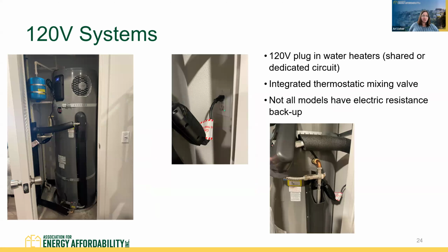120-volt systems. Now, these are pretty interesting because it's essentially a plug-in heat pump water heater. Can be plugged into either a shared or dedicated circuit. There are different options out there. And oftentimes they do have an integrated thermostatic mixing valve. So the hot water can be stored upwards of 120, up to 130 or so. And the integrated thermostatic mixing valve is going to mix it down to delivery temperature. But the thing about these is not all models have electric resistance backup. In fact, many do not. So it really becomes important to manage ventilation and install location.